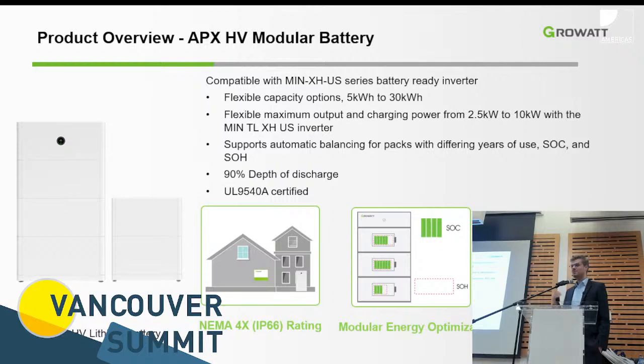It's also a very interesting part specifically for future upgradability, since you have a parallel configuration where every module feeds in on its higher DC voltage level. You can buy a system today with 2 modules, and 5 years down the road, the manufacturer is probably not using the same cells in the battery module they have today, because the industry is growing, there's higher density, probably more capacity available, everything moves forward. But with the actual battery chemistry in the module separated by the DC to DC stage from the output, you can add a battery module 5 years later that is a different chemistry, and it would work pretty much exactly the same way without any effect on the existing battery modules. You would not have that with a conventional series connected high voltage system, because you need to have the same chemistry and the same voltage parameters and ideally the same capacity for that module going forward.